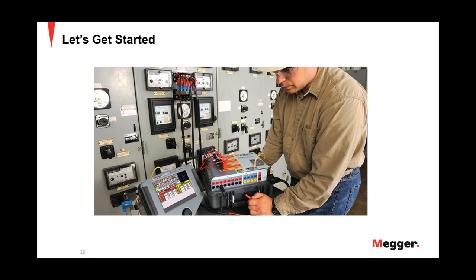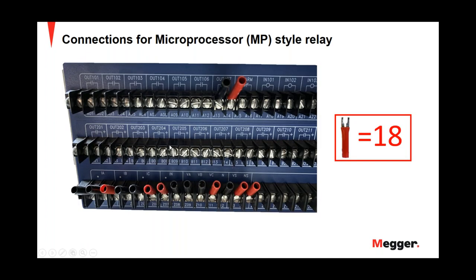Before we get into the software and start creating tests, let me tell you about my setup. I'm using a SMRT 46D and the relay I have is the 351S relay. I'm using fork lugs tied to the back of the relay for my output, and also for my currents, voltages, and power supply. I'm doing a hook straight to the wall for the 120-volt supply. There are 18 total fork lugs I've used for this wiring on this relay.